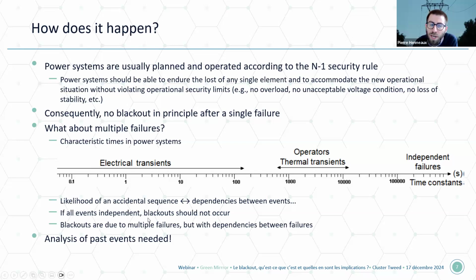So it means that if all events are independent, blackouts should not occur in a power system because operators would have time to correct the situation. Following a first contingency, they would have time to re-prepare the system to face another contingency and to put the system back in an N-1 secure state. Based on this reasoning, blackouts must be due to multiple failures, but with dependencies between failures. Otherwise, operators would have time to correct the situation. They will not just wait for multiple failures leading to a blackout. And so to understand these dependencies, what kind of dependency we can have, we need to analyze past events.